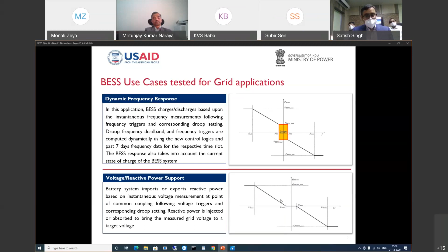The other one is reactive power support. We understand batteries can provide active and reactive power both from the same DC power. Here again, the deadband concept is there. For example, if 0.97 per unit to 1.03 per unit is the voltage deadband range, any deviation from that voltage would be compensated by the battery in terms of absorbing or supplying reactive power support to the grid.